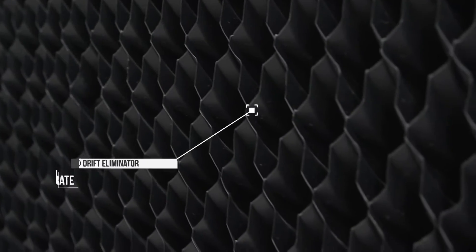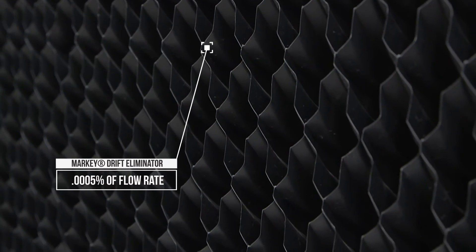In environments like hospitals and universities, you know how critical it is to eliminate drift. It's important to catch these water droplets before they leave the tower to make sure they don't land on adjacent buildings, parked cars, or even people. You're looking at the new Marley MarKey Drift Eliminator. The MarKey allows for the lowest measurable drift rate, down to .0005% of the circulating flow rate.